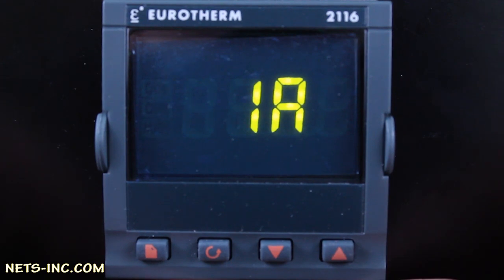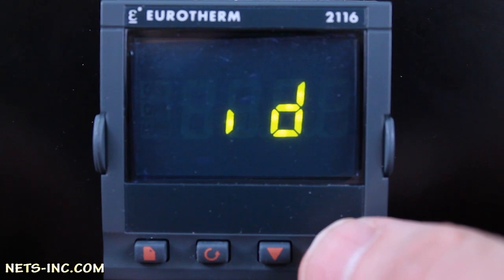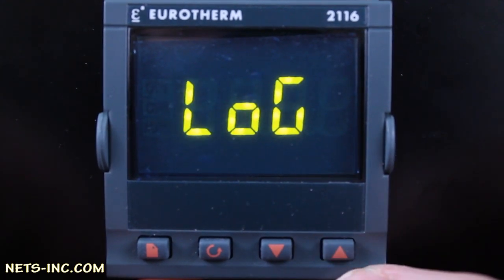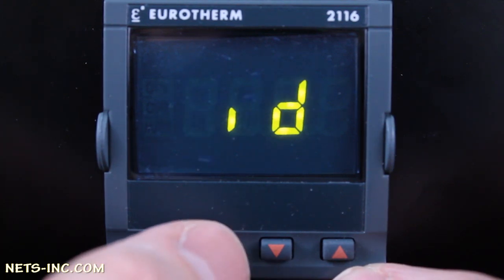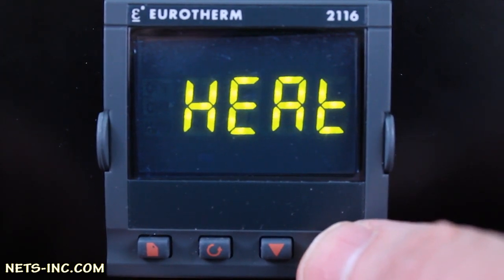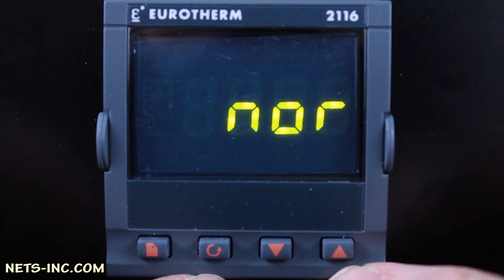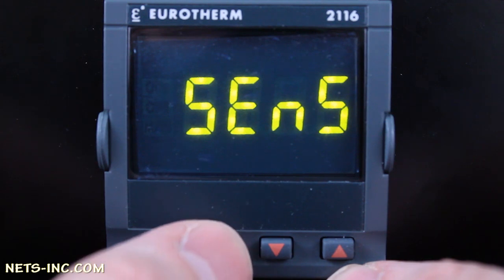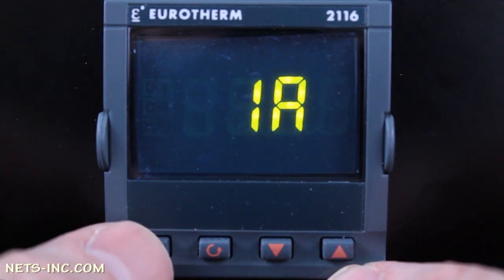Next, press the Page key once to advance to the 1A list. This is the 1A logic output on terminals 1A and 1B — this output will be set up as the heating output. Press Scroll once to drill down into the 1A setup list. The display will read 'id'. Press the Up Arrow to verify that ID equals LOG, or logic. Press Scroll once and the display will read FUNC. Press the Up Arrow repeatedly to change FUNC to HEAT. Press Scroll and the display will read SENS. Press the Up Arrow to ensure the display reads NOR, or normal. Press Scroll once and you are back to the display reading 1A.